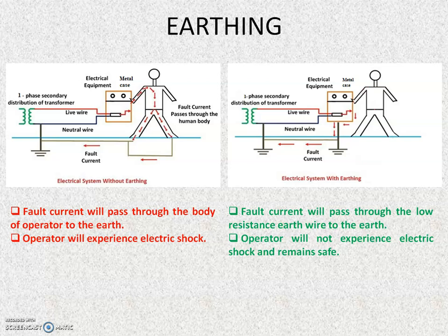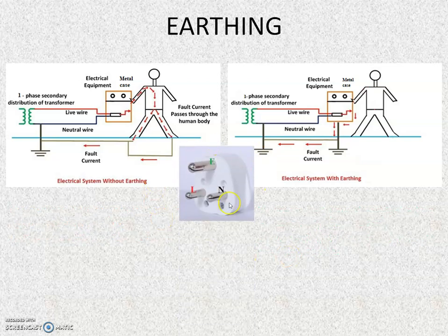Now let us see how this is done in an electrical equipment. You might have seen a 3-pin plug connected to the electrical equipment which is plugged into the socket. These two pins are for live and neutral connection. Normally current enters through the live conductor and returns through the neutral conductor. Then we have introduced an earth connection or earth pin, and in this case the earth pin will be connected to the metallic case. So the earth is always connected to the metallic case. And you can see from the structure itself, the earth pin is different when compared to the other two pins. The size of the earth pin is big and it is also longer. So when we are inserting it into a socket, the earth will come into contact first.